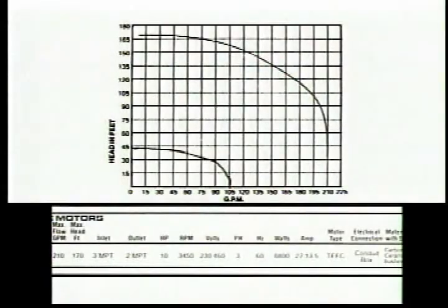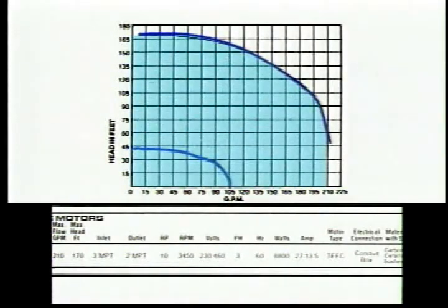You can see this visually on the pump chart when you compare the total area under each of the performance curves. The area under each curve corresponds to the power required to achieve the head and flow capacities indicated by the curve. This area is just 1/8 as great as this area, so operating at any point on this curve will require 8 times as much power as operating on this curve.